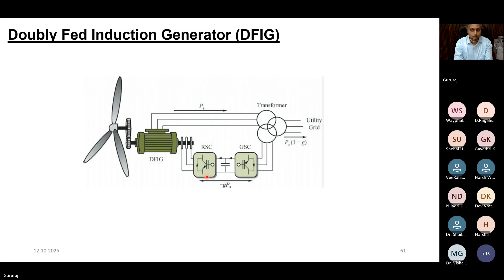As you can see, you sense the signals and then convert from ABC to DQ frame. The objective of the rotor side converter, my dear friends, is to extract maximum power from the turbine. I'll explain how we do it. There are 2 degrees of freedom, D control and Q control, both available for the rotor side converter and the grid side converter. With the help of D control, we adjust the power factor or try to inject reactive power. With the help of Q control, we track the MPPT here. In the case of grid side converter control, with the help of the D axis we adjust the active power, and with the help of Q control we do the reactive power management. So how we do the MPPT tracking is what is important.